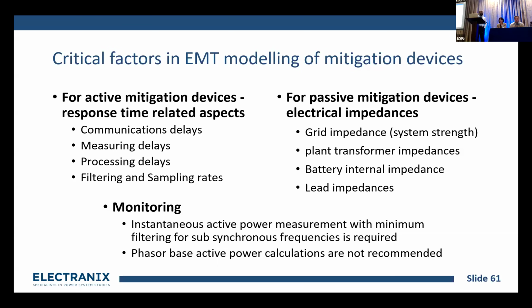So these communication delays, as Arman mentioned in his presentation, the values that we put in are a guess value. It's not a value that we can say is 100% going to be the worst case. In other terms, we can put in a communication delay that is kind of the worst case. We know the actual one will be faster than that, so we are good. We are going to the good side there.